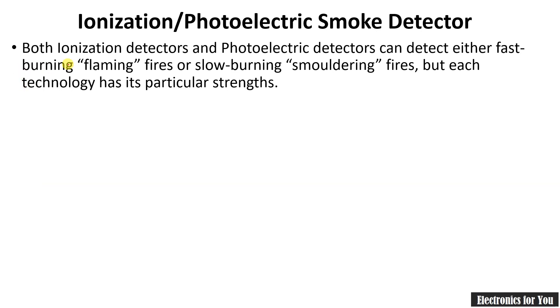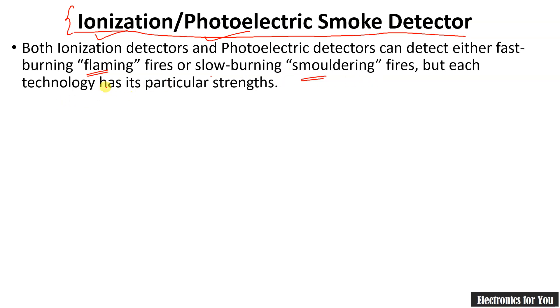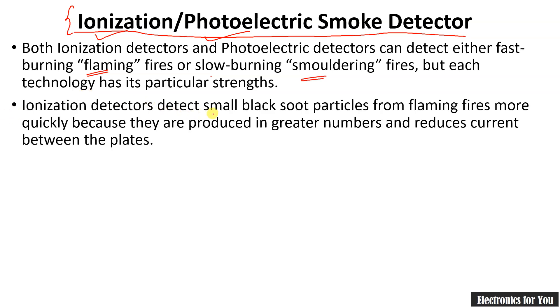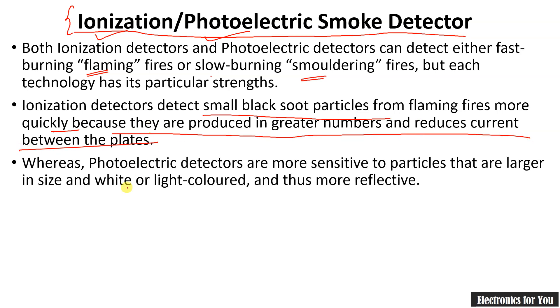The next type is the ionization-photoelectric smoke detector, which is a combination of the ionization and photoelectric smoke detectors. The ionization smoke detector can detect flaming fires, whereas the photoelectric detector can detect smoldering fires — so each has its own strengths and weaknesses. The ionization detector detects small dark smoke particles from flaming fires quickly, as they are produced in greater numbers and reduce the current between the plates.